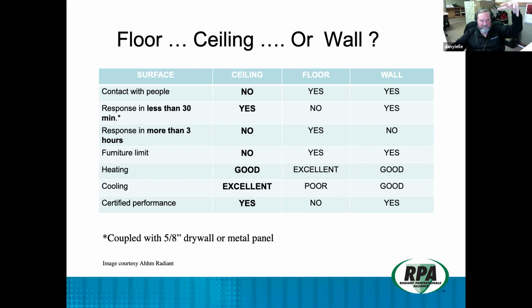Well, there's a cold source there. It absorbs that heat. Basically, all you have to worry about at that point is being able to handle the latent energy, which you can do with dehumidification or a cold coil, some means of being able to control the humidity within that space and keep it away from the dew point. All of these manufacturers that put these controls out are basically watching the dew point, and they can do one of two things. They can either manipulate the dew point by reducing the humidity or manipulating the temperature of the surface itself. Ideally, if you control the humidity, you'll never find your panel anywhere near the point of condensation.